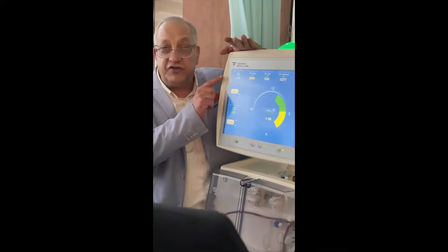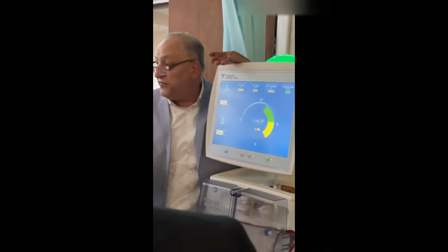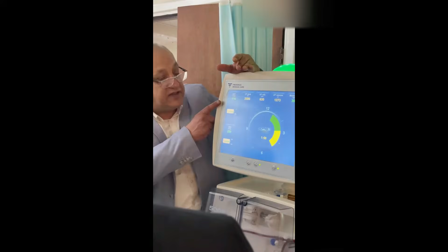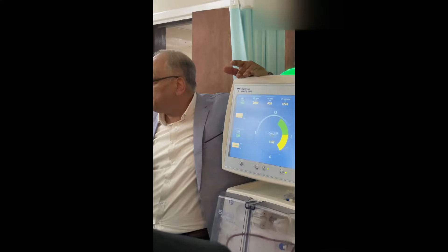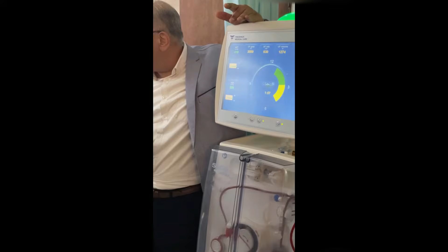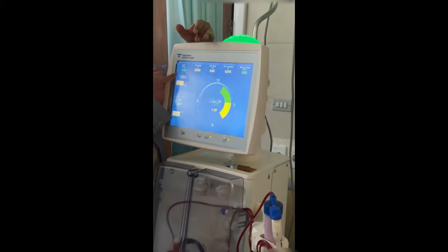If you have below 200 millimeter mercury on a blood pump around 250 and 300, so we have a good functioning system. If you have a negative pressure, for example, above 250 millimeter mercury on a blood flow around 250, you will have suction and interrupted flow, air, and subsequently complications. So the first parameter is the arterial negative pressure that measures the functionality of the vascular access. I can consider in this patient it is good.